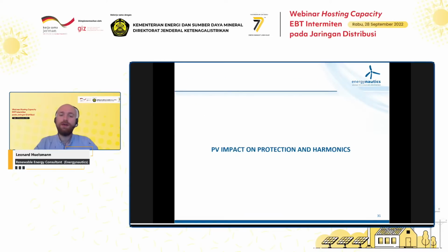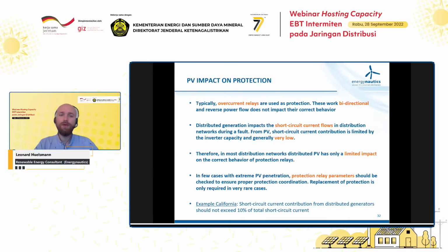We have also certain impacts on protection and harmonics. I only want to briefly show this. So there's also certain impacts that distributed PV may have on protection. However, it's a very technical issue, and I don't want to go into the details of this, but basically what we observe is that PV systems, due to being connected through an inverter, have only very small short circuit current contributions, and that basically means that their impact is actually limited and lower compared to maybe other types of distributed generators. And so generally what we observe is that there will be only a limited impact on the correct behavior of protection relays.